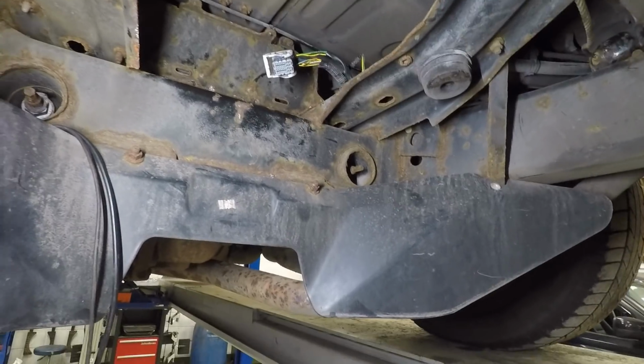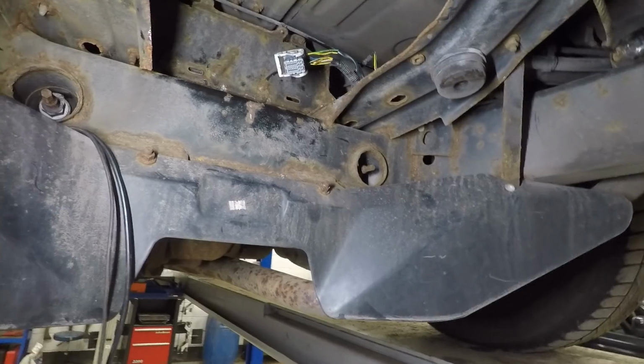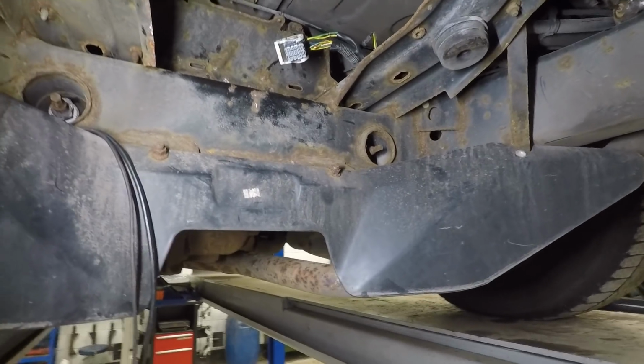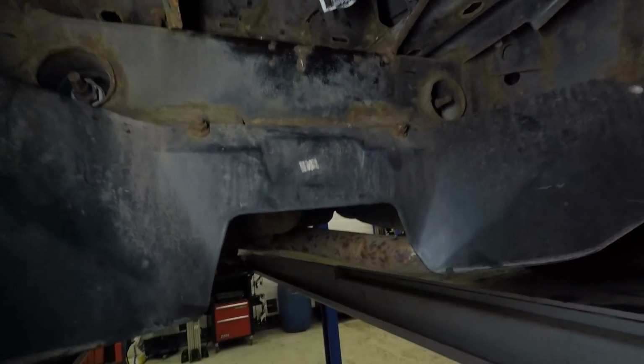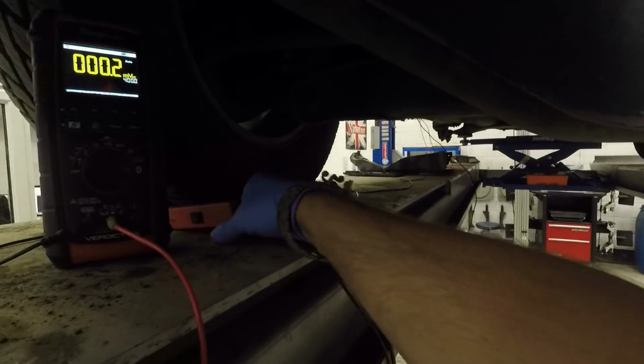It's got power, it's got ground, it communicates, but it just doesn't activate the motor. At that point, just to find out what exactly was wrong, you could say the whole module is faulty, or you could say the module is faulty because the motor itself is dead.